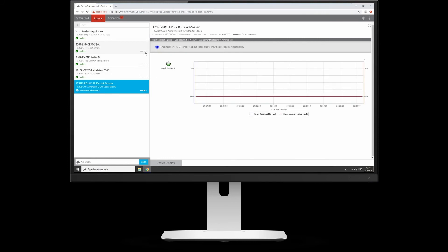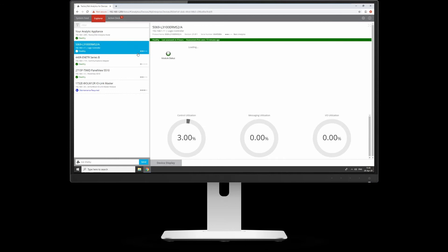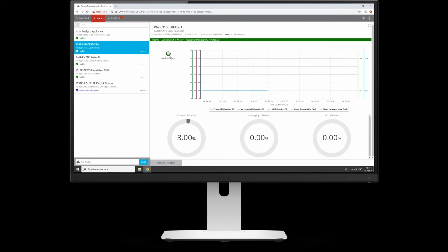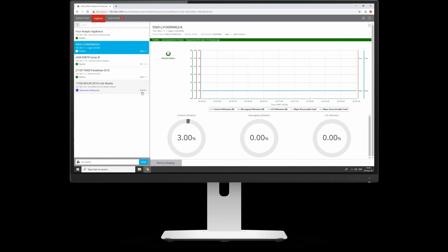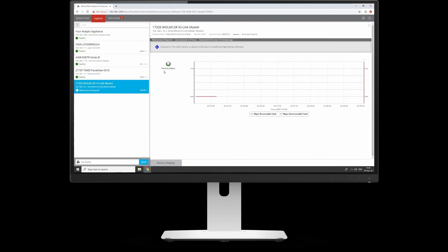If you look on the side there, there's some bars. For the PLC, it's only got two out of four bars of diagnostic information. If you go in there, it says it's healthy, it's got this much utilization—a quick overview. There's not much information it's going to get out of the PLC. But with the IO-Link, you've got three out of four bars, so it's giving you more data.